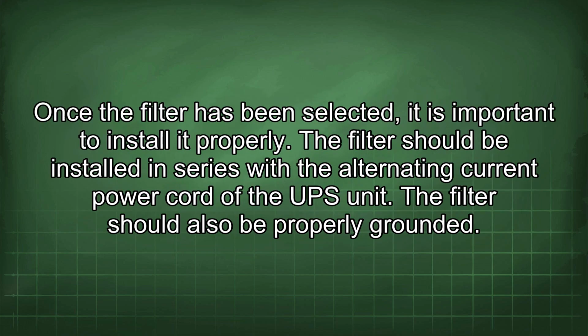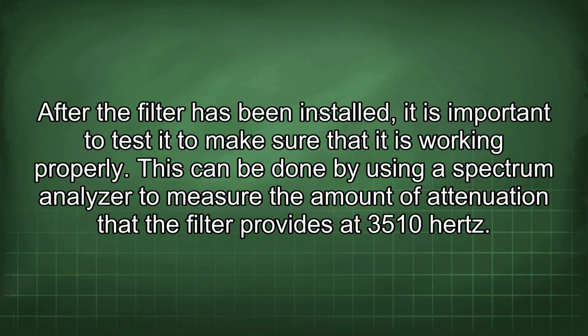Once the filter has been selected, it is important to install it properly. The filter should be installed in series with the alternating current power cord of the UPS unit. The filter should also be properly grounded. After the filter has been installed, it is important to test it to make sure that it is working properly. This can be done by using a spectrum analyzer to measure the amount of attenuation that the filter provides at 3510 Hz.